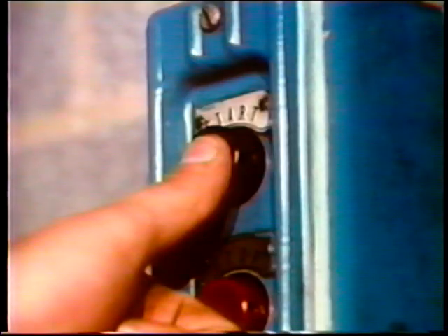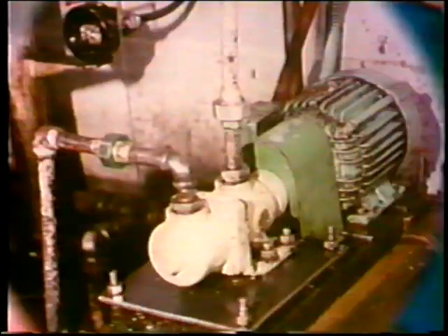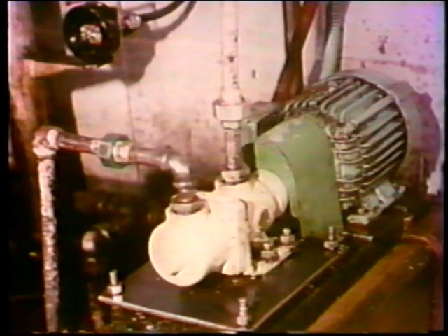The electrician must do the sixth and final step in troubleshooting, test. The electrician must test the controller to make certain it is now operating correctly. He asks the operator to test run the pump. The operator pushes the start button and the motor starts. He monitors the operation and makes sure that the pump stops when it should. It operates normally. The problem has been solved.